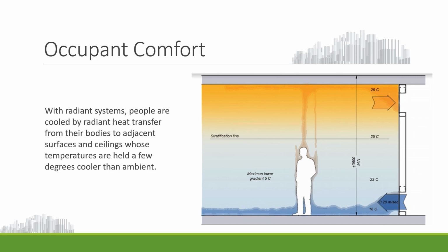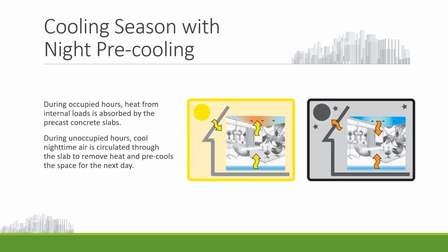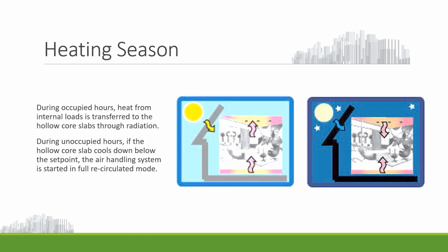This is just a depiction of how the concrete can absorb the energy from a human being or from lights or equipment. So during occupied hours, heat from internal loads is absorbed by the precast concrete slabs. And during unoccupied hours, cool nighttime air is circulated through the slab to remove the heat that was stored during the day from the equipment and the bodies and the occupants of the building, and it's pre-cooling the space for the next day. In heating season, during occupied hours, heat from internal loads is transferred to the hollow core slabs through radiation. During unoccupied hours, if the hollow core slab cools down below the set point, the air handling system is started in recirculation mode.